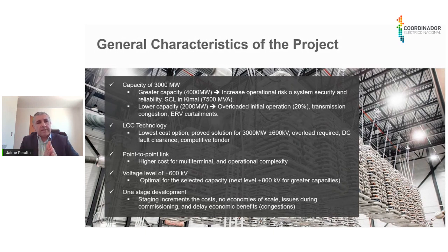Then, why LCC technology? We did the technical and economic evaluation and arrived at the conclusion that it's the lowest cost option, an approved solution for the level of capacity and voltage level that we're proposing, which is 3,000 megawatts and ±600 kV. And we also require some overload to the system to comply with the N-1 criteria in the system, which is limited for the VSC technology. And also we have a minimum time to recover from DC faults that is also complicated to achieve by VSC technology at this level of capacity.